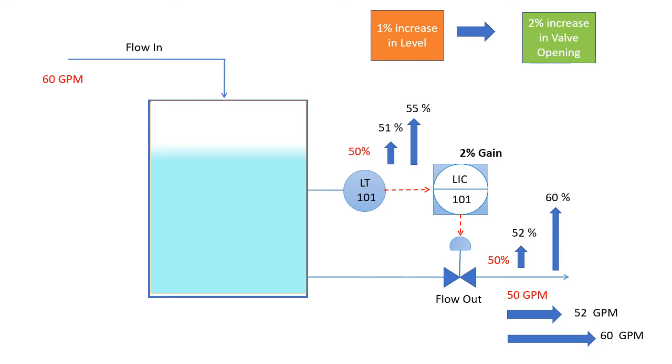So our initial target was 50 percent. Now we are stuck at 55 percent. And at this moment, as flow inlet is equal to flow outlet, there is no further change in level. So there is a 5 percent offset from 50 percent to 55 percent. So how can we minimize this offset?